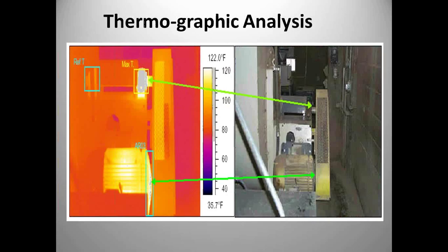Mechanically, looking at a motor and bearing while walking through a plant, we don't see anything — but easily with the camera we see a temperature rise. Not a big temperature rise, but easy to find that we have an issue. If we monitor this month to month and understand what that temperature is, it may be telling us we need to add some lubricant to the component. These are failures we can map back using thermography as a tool to find mechanical failures.